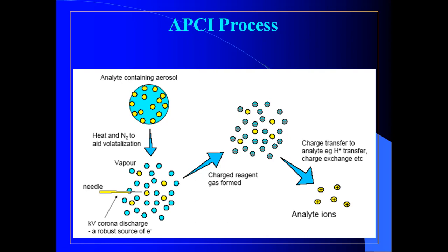When the sample introduced through the APCI is sprayed into the heated probe with the aid of nebulization gas, within this probe the finely dispersed droplets of the sample and solvent undergo a rapid vaporization with minimal thermal decomposition. The gentle vaporization preserves the molecular identity of the sample basically.